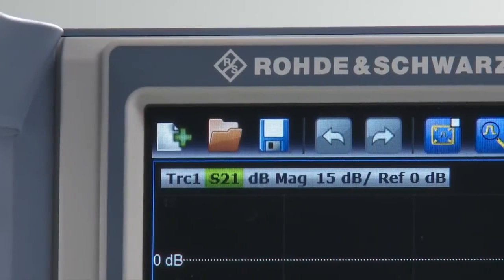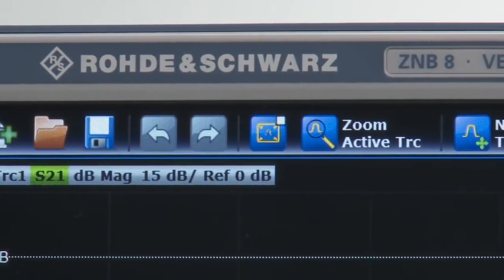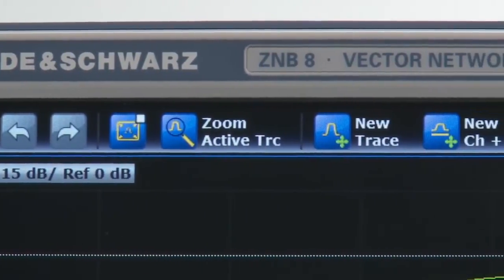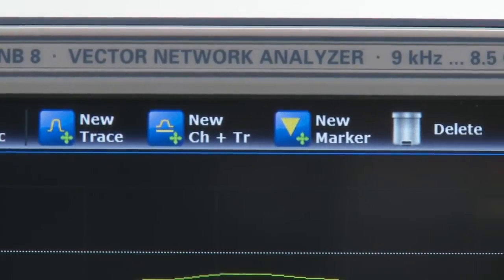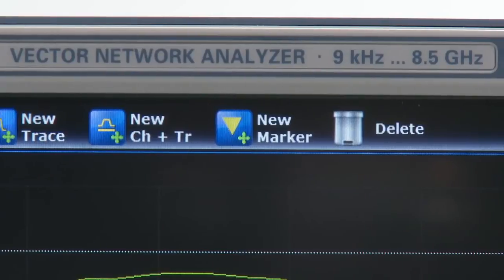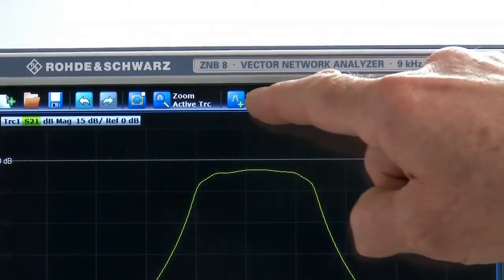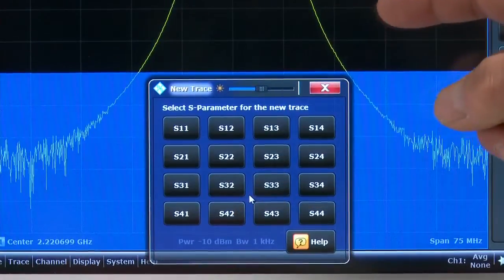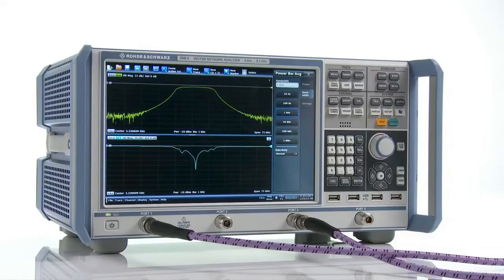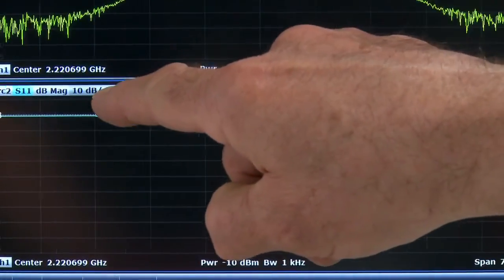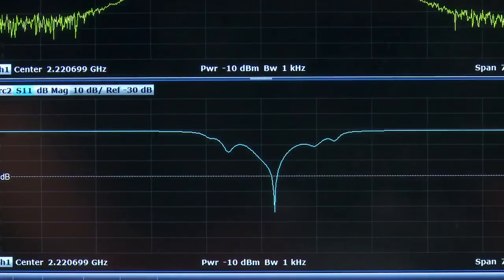The ZNB has another soft tool, the toolbar, that gives fast and easy access to frequently used functions. Need another measurement trace, for example matching, which is S11? Just tap on the corresponding icon and drag the window where you want. A double tap on the trace info bar auto-scales the new trace and analysis can begin.